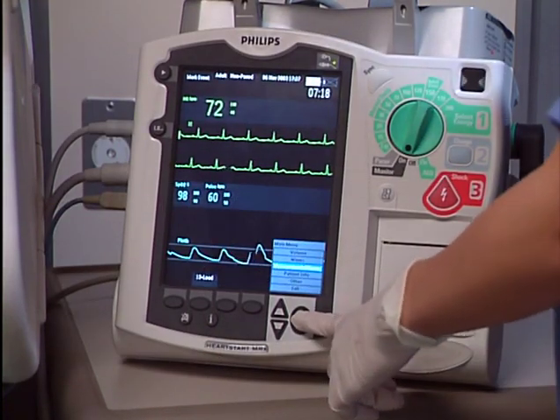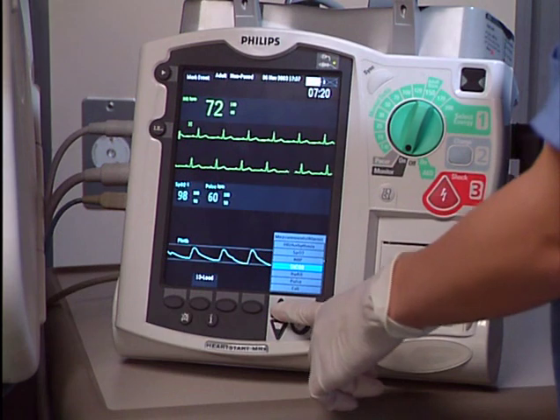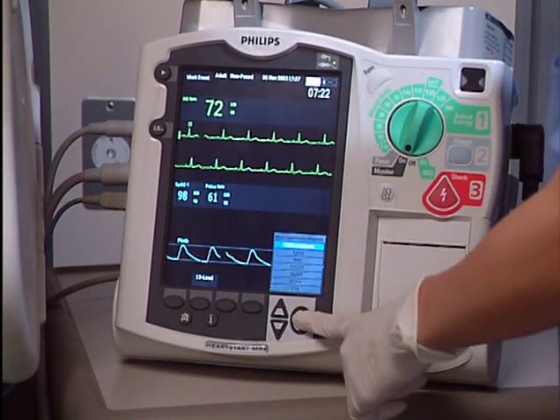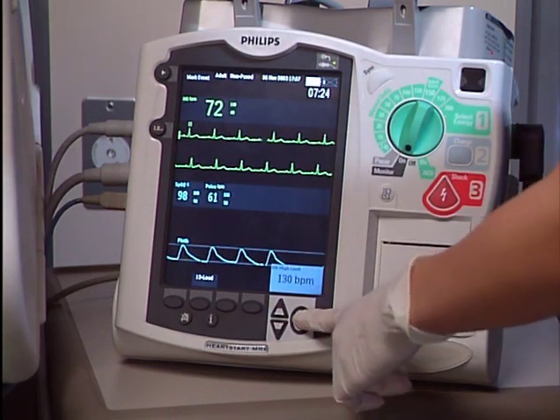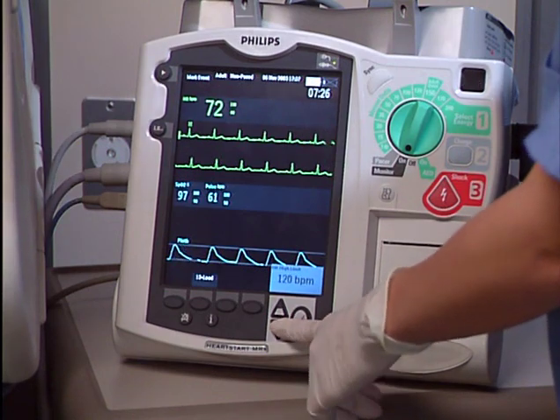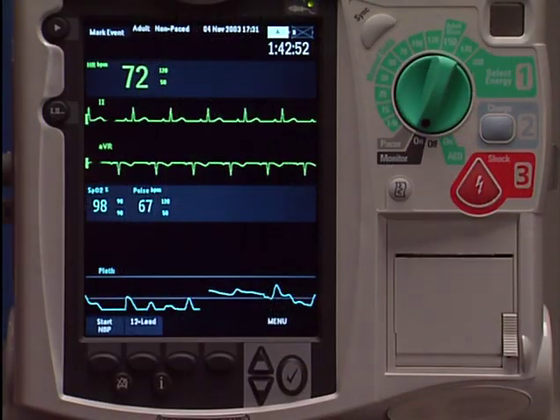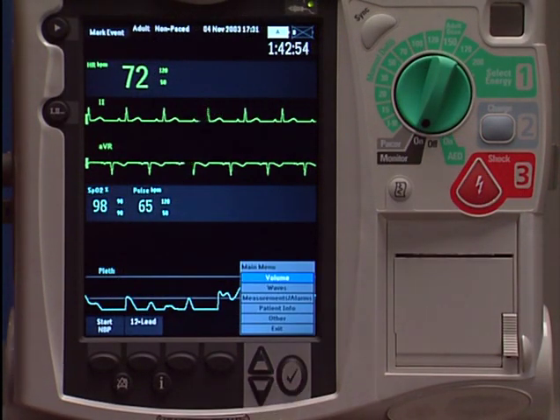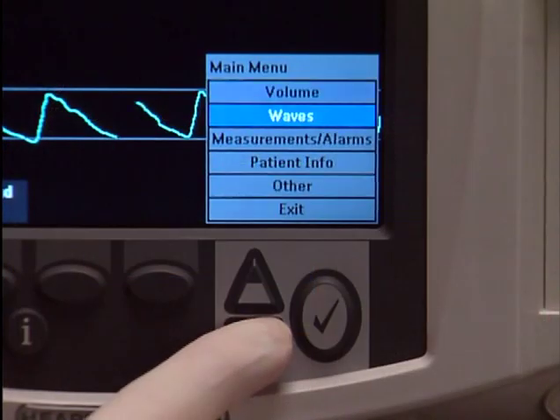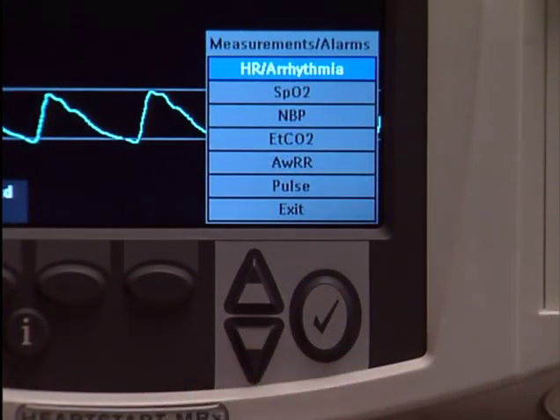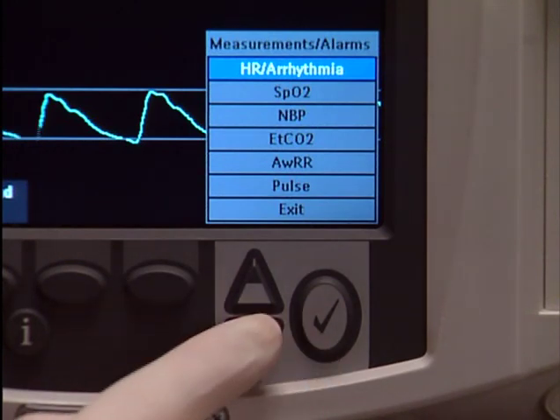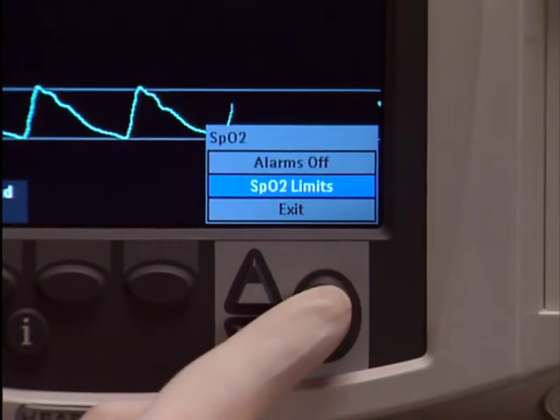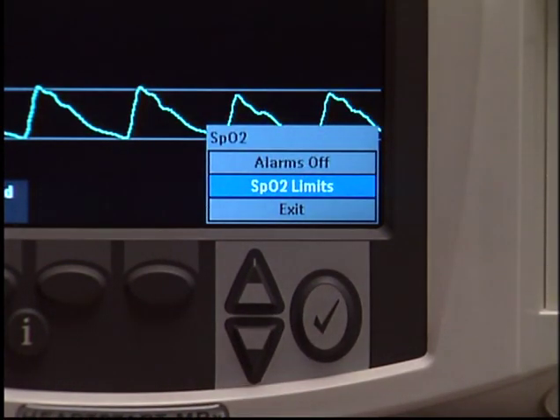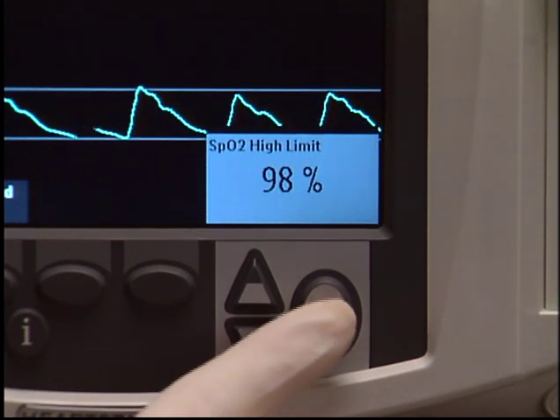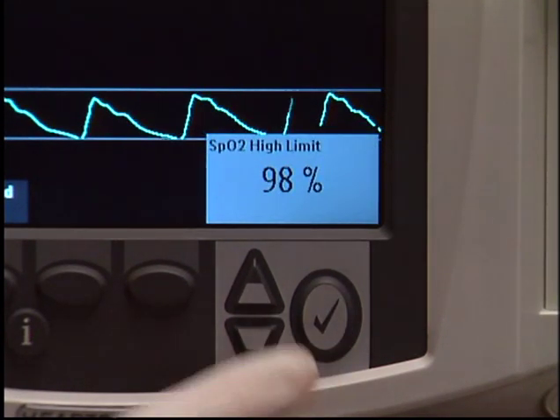Setting high and low alarm limits and turning alarms on or off is the same for all measurements, so let's look at how to do these tasks using pulse and SpO2 as examples. To set the high and low limits, press the menu select button. Navigate to Measurements Alarms, SpO2, and SpO2 Limits. The high limit appears in this window.